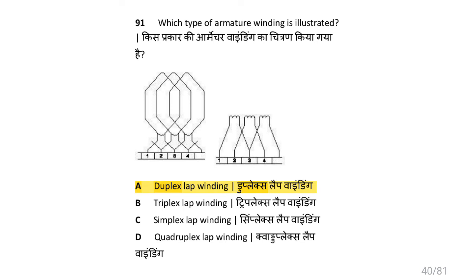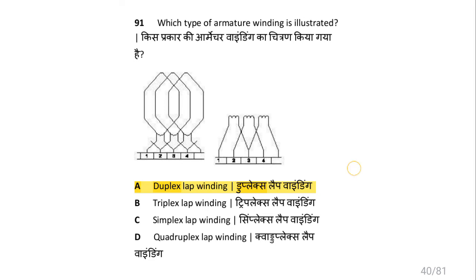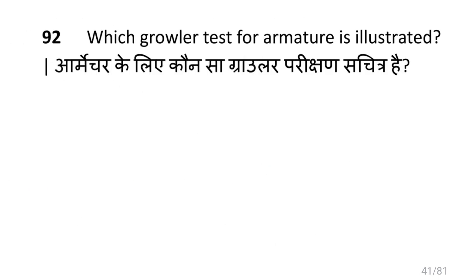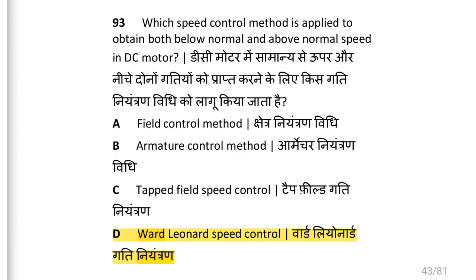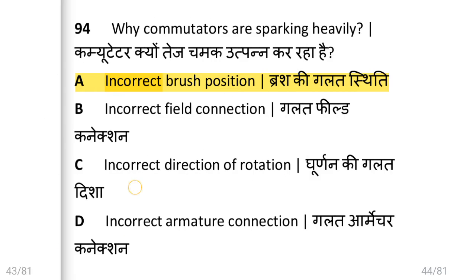Which type of armature winding is illustrated? That is duplex lap winding. Which growler test for armature is illustrated? That is open coil test. Which speed control method is applied to obtain both below normal and above normal speed in DC motor? That is Ward-Leonard speed control.